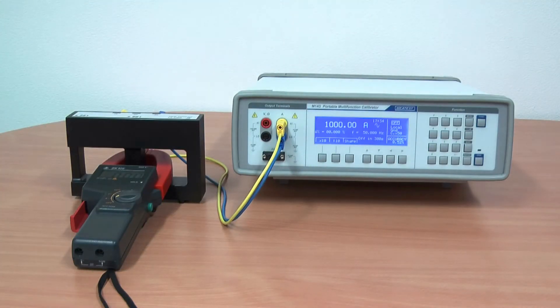50 turn coils can be utilized for calibration of clamp meters up to 1000A. Let's try it out.